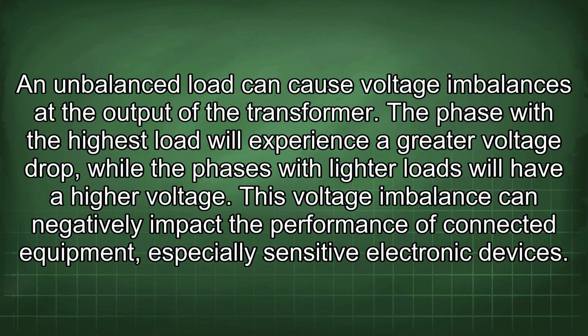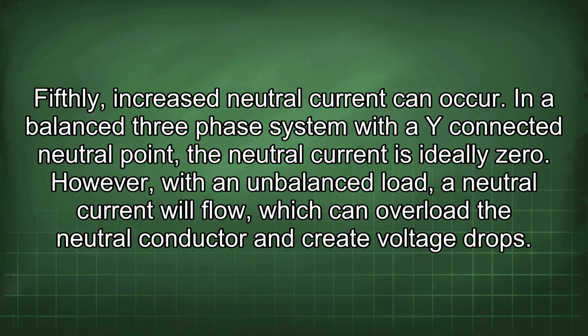Fourthly, voltage regulation suffers. An unbalanced load can cause voltage imbalances at the output of the transformer. The phase with the highest load will experience a greater voltage drop, while the phases with lighter loads will have a higher voltage. This voltage imbalance can negatively impact the performance of connected equipment, especially sensitive electronic devices. Fifthly, increased neutral current can occur. In a balanced three-phase system with a Y-connected neutral point, the neutral current is ideally zero. However, with an unbalanced load, a neutral current will flow, which can overload the neutral conductor and create voltage drops.